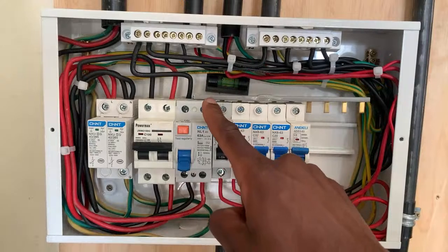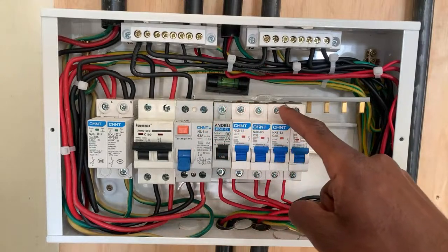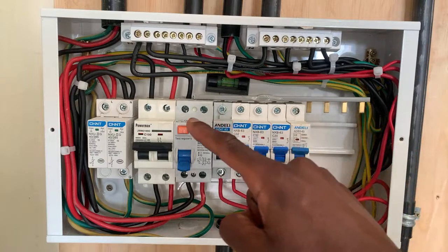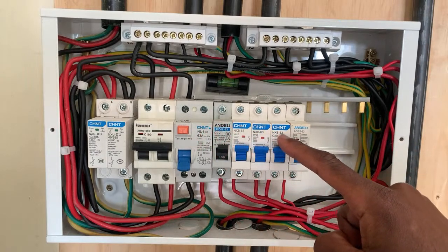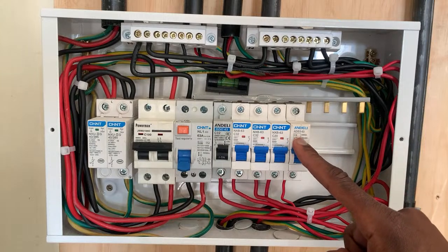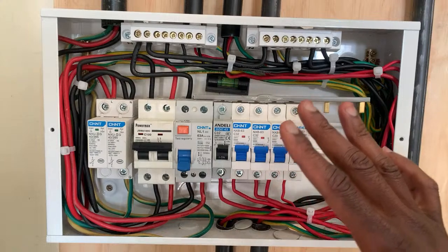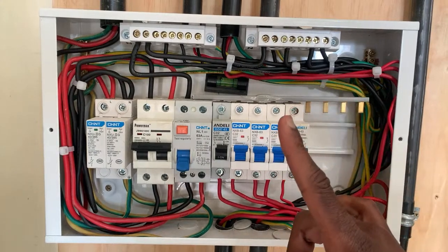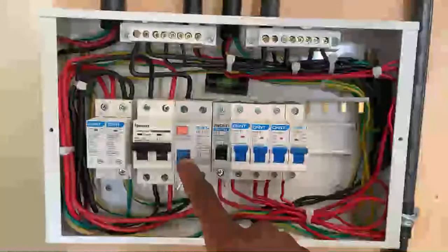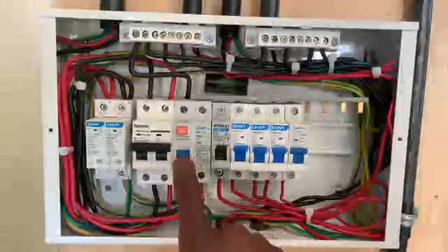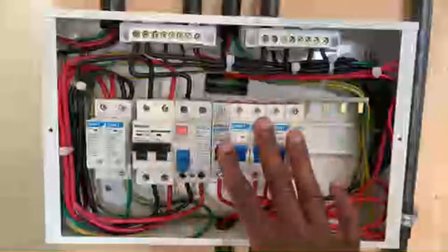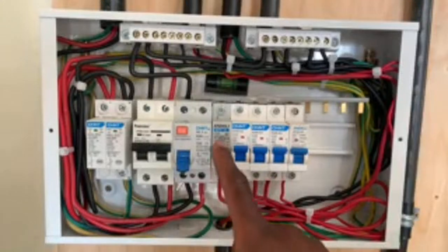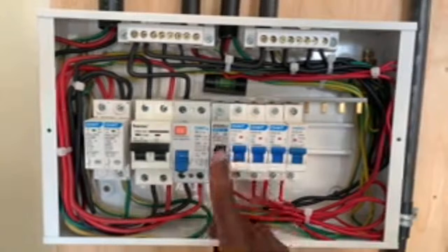And when it trips, it cuts off the supply of electricity to this bar here, meaning all of these circuit breakers will not receive electricity supply. So you stand a chance to be saved from an electric shock if cut RCCB. When it comes to the heating circuit, it is important to note that whatever gadgets you have here matters a lot. If you have a circuit breaker that is faulty, then there is a problem, because it will not trip in case there is a problem.